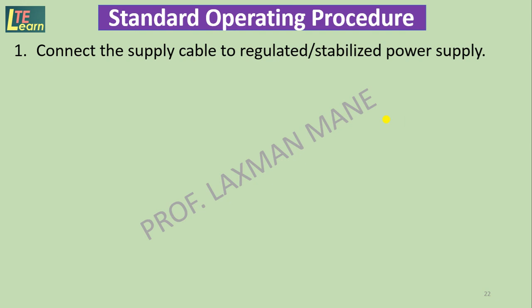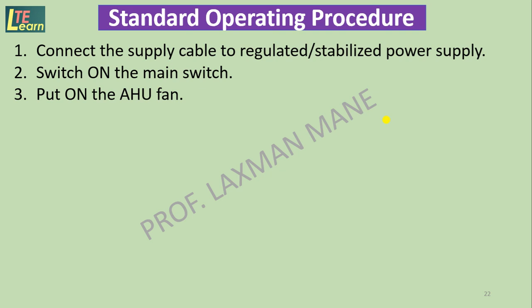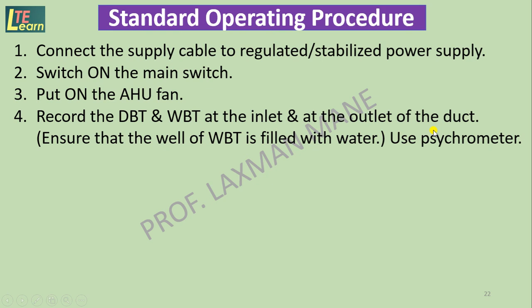Standard operating procedure. Connect the supply cable to regulated or stabilized power supply. Switch on the main switch. Put on the air handling unit fan. Record the dry bulb and wet bulb temperature at the inlet and at the outlet of the duct by using a psychrometer. Switch on the compressor and allow the system to reach steady state.